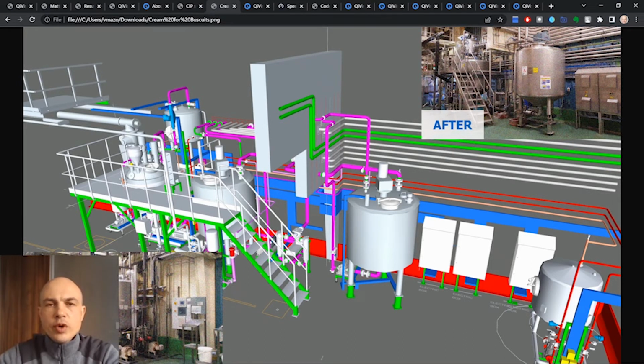Another case is about a project we did in Spain for cream preparation for biscuits. During commissioning, we faced similar issues as with the CIP system, plus the existing equipment was integrated into a quite old proprietary SCADA system. In order to solve the issues and failures that happened, I had to look at the HMI panel on our equipment, then go to another room to watch the SCADA system, and go even to another department behind the wall where the tempering machine was receiving the product.